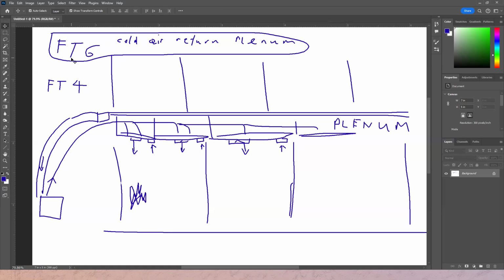If it's free air wiring in a cold air return plenum, then you have to use FT6 cabling. And the inspectors pay close attention to that. Their eyes are so keen they could just look and say, oh, that looks like FT4 cable, it should be FT6. They will make you pull that out at your own cost, and you still have to fulfill the contract. You're going to have to reinstall it, so it's going to cost you way more. If you're trying to get away with that, please don't, because it's going to create all kinds of unpleasant situations, financially unpleasant as well, because you can get fined for that.